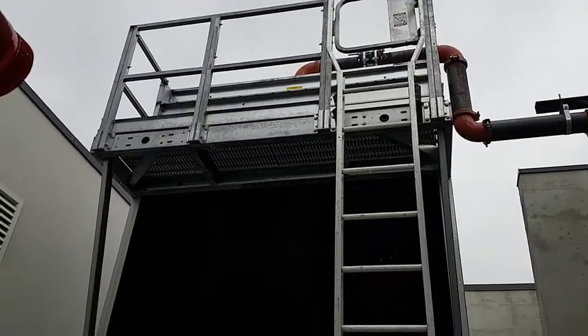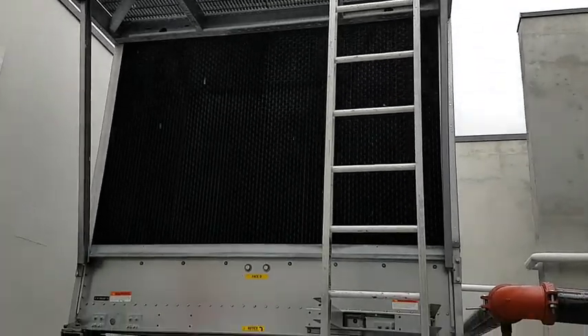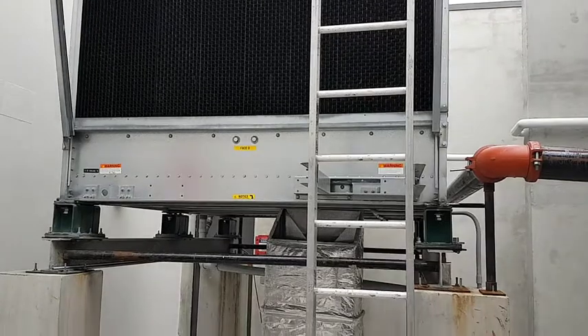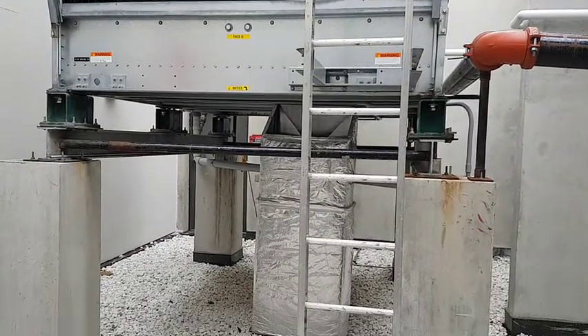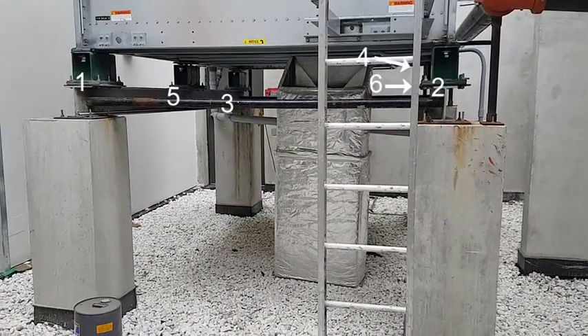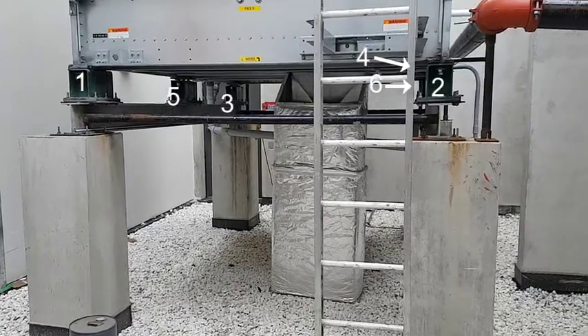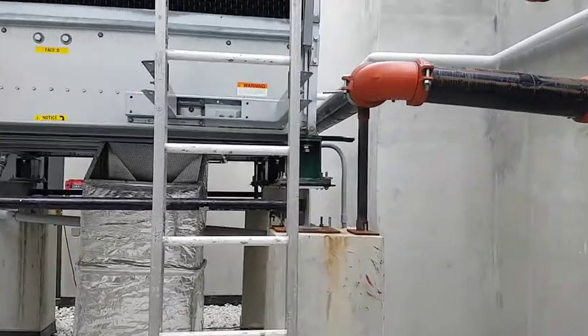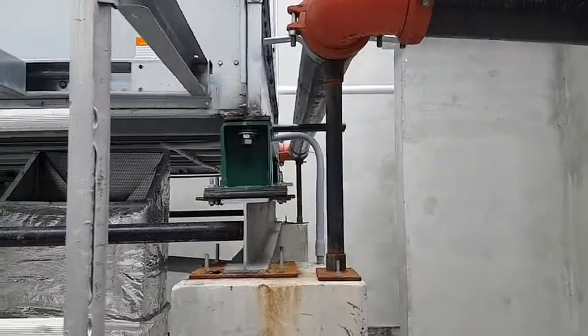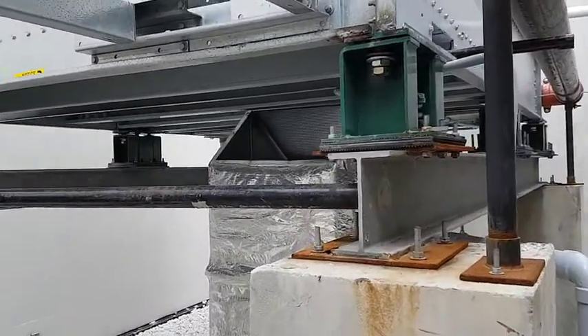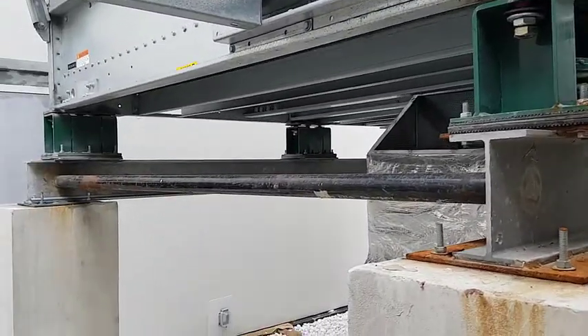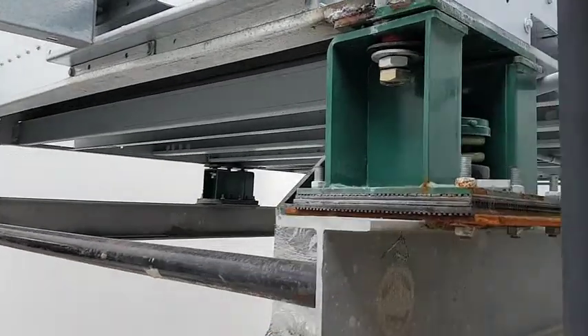This is the air inlet side of the cooling tower, and as explained earlier, it does not sit on a steel support base but instead sits directly on the isolators, labeled here to correspond with the locations shown on the datasheet. As we approach the tower, everything appears to be stationary, straight, and level, so we can inspect the isolator safely. That's location 1 over there, but we'll look at location 2 first.